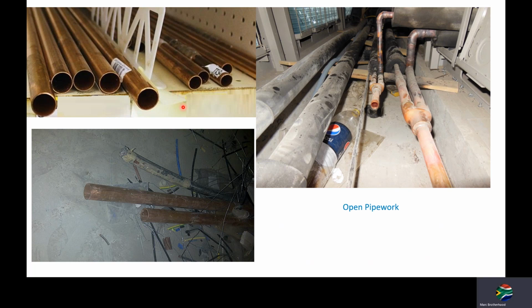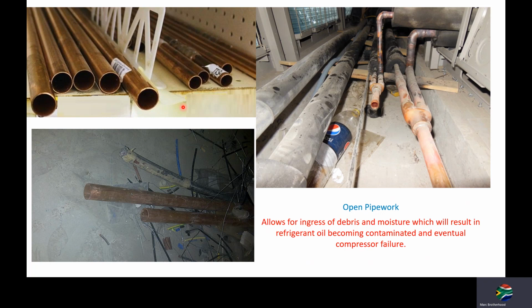Here we can see a site where there's just open pipework in the field. So what's this going to do? It's going to allow for an ingress of debris and moisture, which is going to result in refrigerant oil becoming contaminated and eventual compressor failure. Here you can see there'll be a lot of dust going into the pipework. When the dust mixes with the oil, it forms a grinding paste, and it will damage the running surface of the bearings in the compressor.